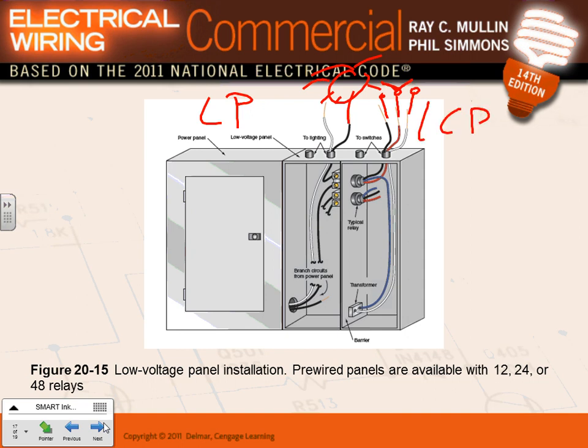Now, Jeff, either you attach them like this or you nipple. You put a little nipple between them, space them like say 6 inches, and put a nipple between them and pull all your conductors. Can you guys see that all the conductors are being pulled in and out? That's how they do them. In our case, because we put them slightly apart, you might have to put 18 inches or 20 inches or maybe 24 inches conduit.